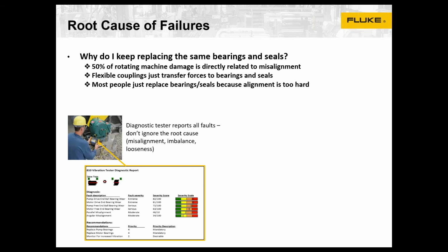One example would be bearings and seals on pumps. A lot of times people think that on coupled machines, if you have a flexible coupling between a motor and a pump, that will solve any issues or mitigate anything related to misalignment. While it's true it won't physically damage the machine or fly apart, misalignment forces are still present, and they're transferred to the bearings and the seals.